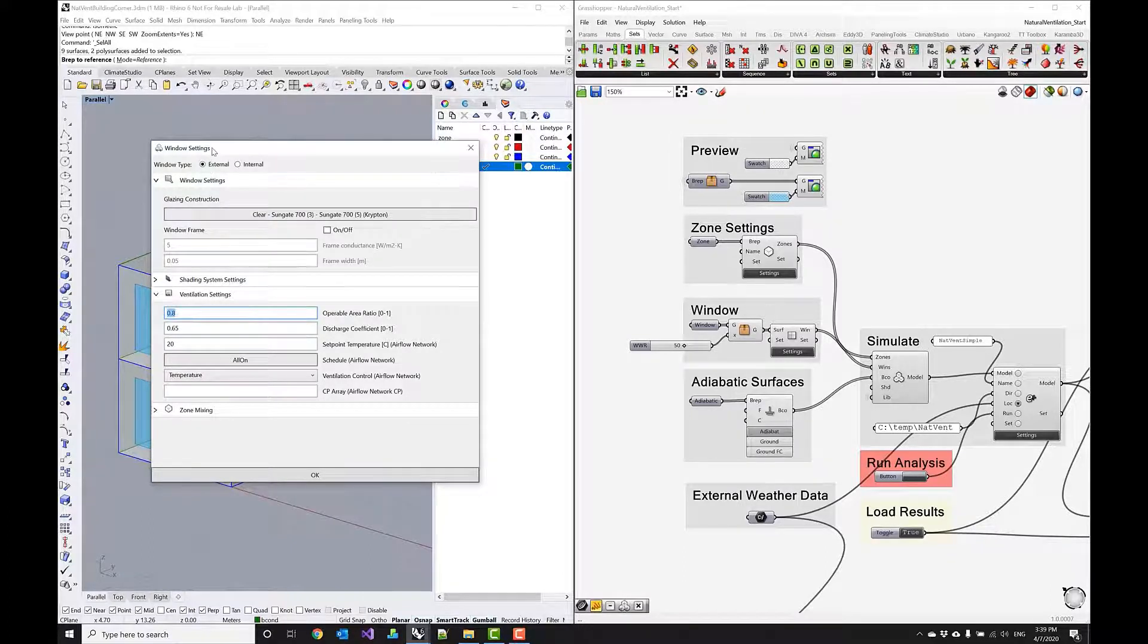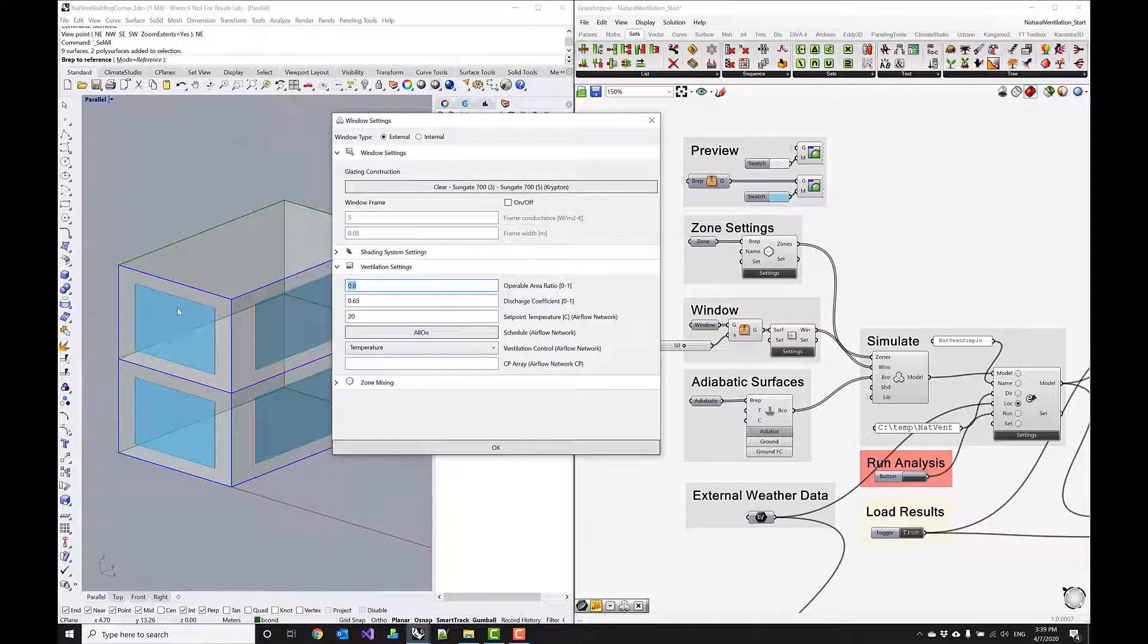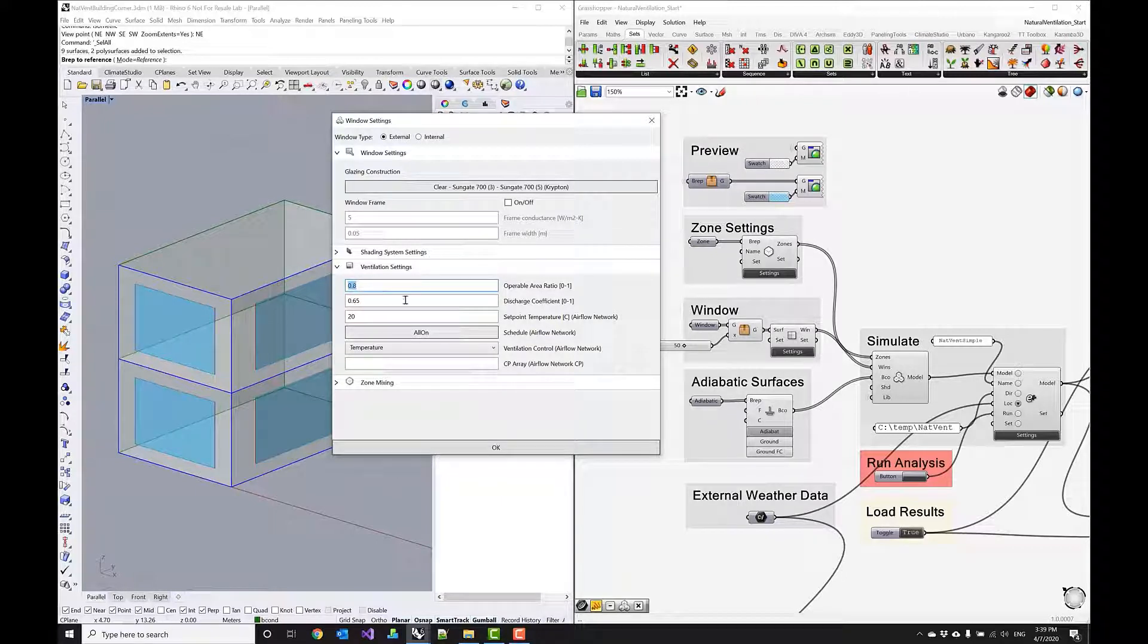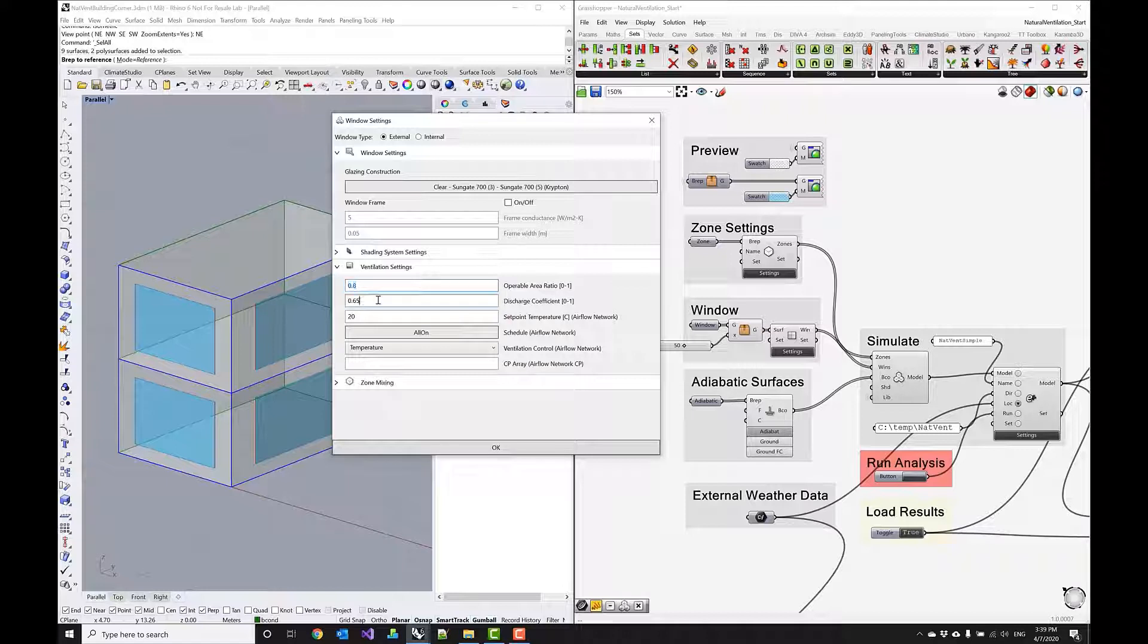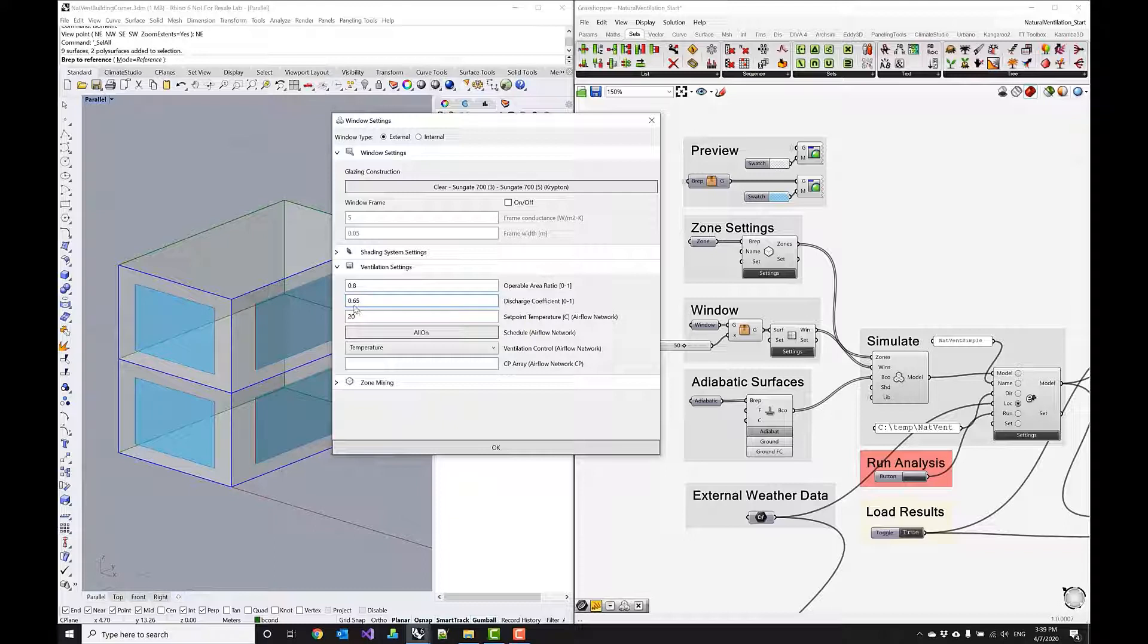show natural ventilation properties in a second. So there's a couple of things that are relevant especially this operable area ratio which controls how much of this surface can actually be opened and in this case we model with 80 percent and then there's the discharge coefficient which for a rectangular opening is in the 0.6 to 0.65 range so this is what we're assuming here.